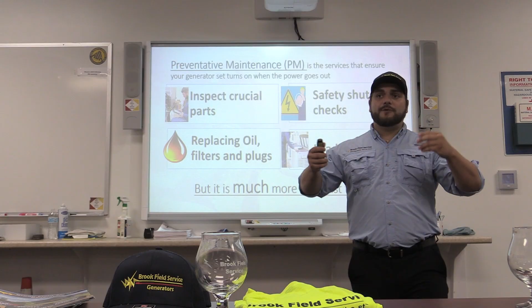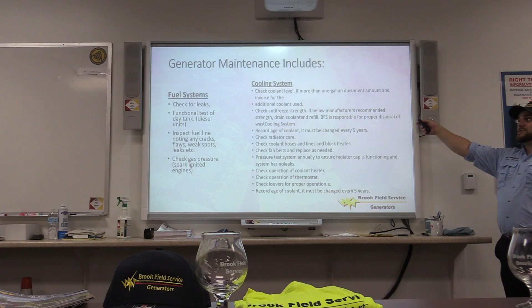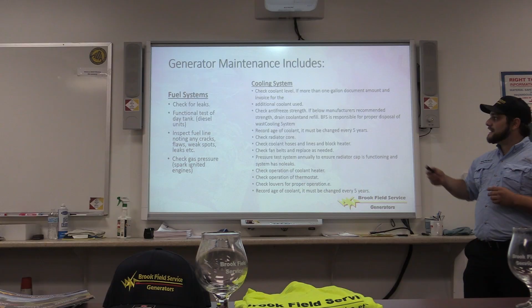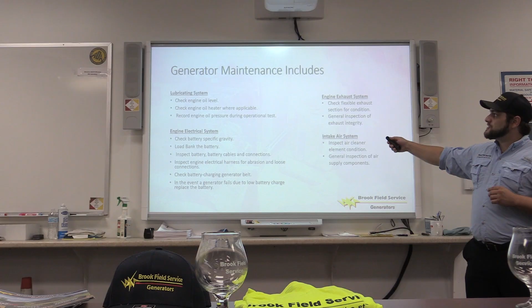I'll briefly go through the things our generator maintenance includes: checking for leaks in the fuel system, checking gas pressure, looking at the coolant system which is one of the biggest issues, checking the radiator core, checking fan belts, checking operation of everything, making sure the coolant is flushed if needed or replacing the coolant levels. These are things you might be able to do, but on the backside you're going to require a certified factory technician for the lubricating system, engine electrical system, engine exhaust system, and intake air system. If you've handled your own generator maintenance, these might be things you don't have a checklist for, aren't inspecting for, or don't have the proper tools for - which is why it's so important for us to come take a look, especially when it comes to the coolant system.